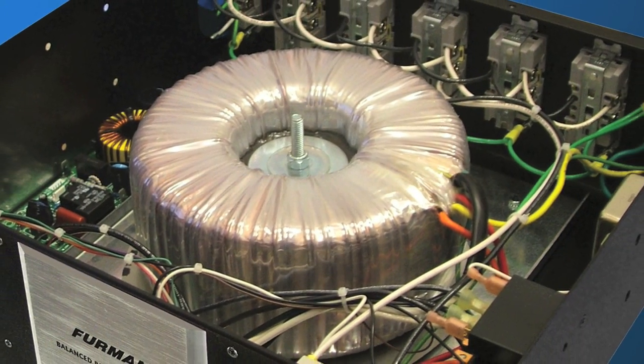Common mode noise, such as ground loops, can be much more difficult to deal with. One real-world, effective solution is the isolation transformer, and the most effective of these are the true symmetrical balanced isolation transformer. Here's how one works.